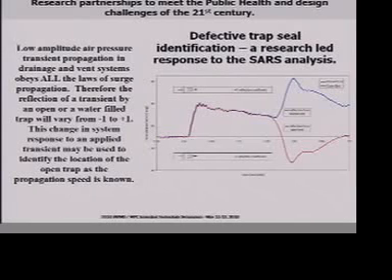And because you know the speed of the pressure wave is 320 meters a second, the acoustic velocity in air, you know the time at which the reflection comes back, you know the speed, so therefore you know the distance. So in other words, if you like, it's a sonar system for drainage systems. It's exactly the same as you see in the movies when people say we've got a blip and somebody is 300 yards to port. That's exactly how it works.